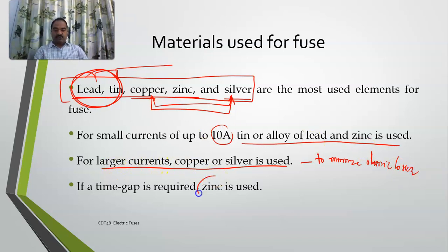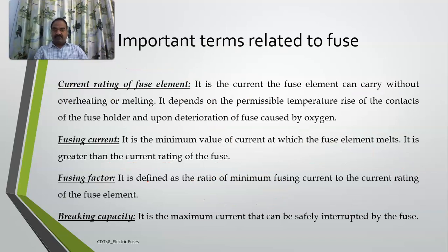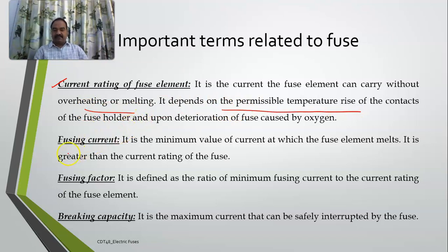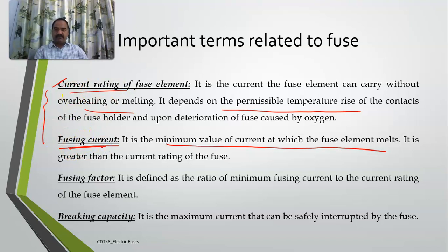If a time gap is required, zinc is the best option. Now the important terms related to a fuse: first, current rating — it is the current which the fuse element can carry without melting, essentially the normal current in the circuit. It depends on the permissible temperature rise and the contacts. Second, fusing current — it is the minimum value of current at which the fuse element melts. It is slightly higher than the current rating.